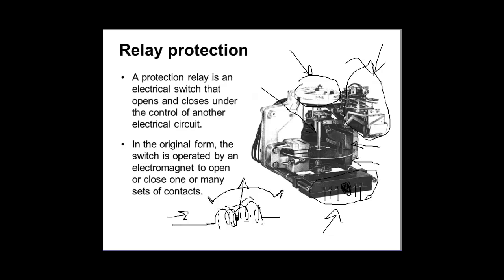And out of that, a DC signal, a DC voltage that was hidden somewhere, is now free to move towards the circuit breaker trip coil. And the circuit breaker trip coil will be energized. That is enough for activating a spring mechanism that is connected to the contacts of the circuit breaker. The spring mechanism will make the two contacts of the circuit breaker get apart, and the circuit breaker is tripped and open.